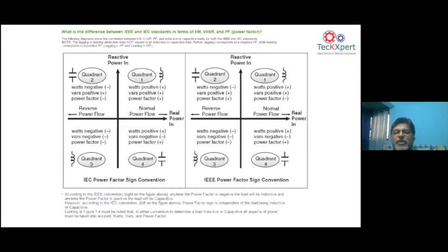I have a certain amount of lagging power factor, a certain amount of kilowatt I'm consuming. But when you go into the export mode, you have a quadrant 3 operation, which is not very good, because in quadrant 3 you create a leading power factor problem. I'm sure TNEB, or any utility for that matter, if you have a solar plant, won't allow me to inject leading power factor to the grid.